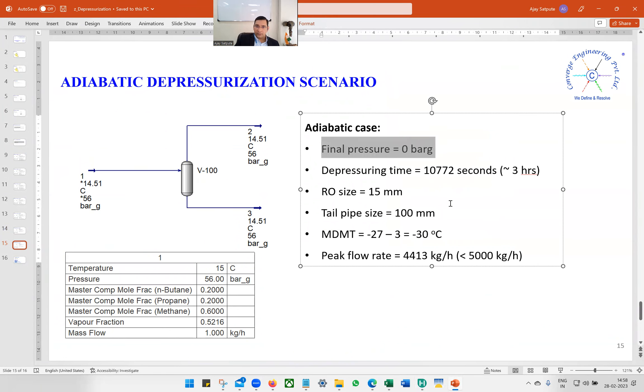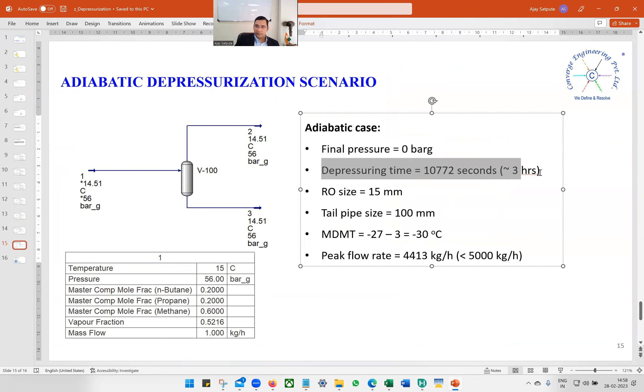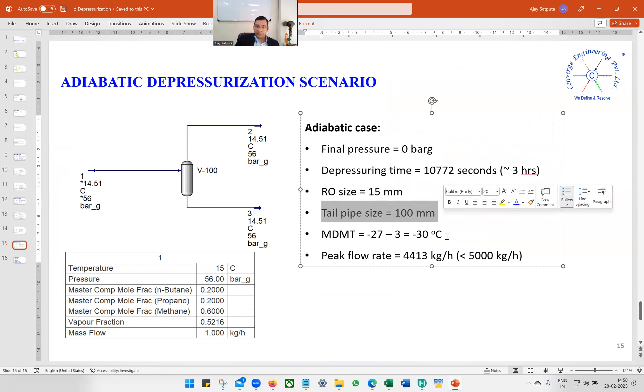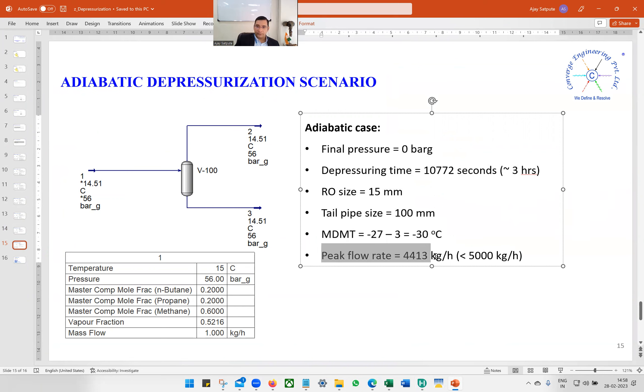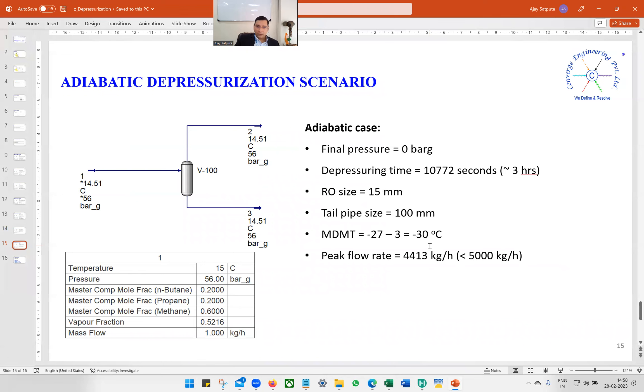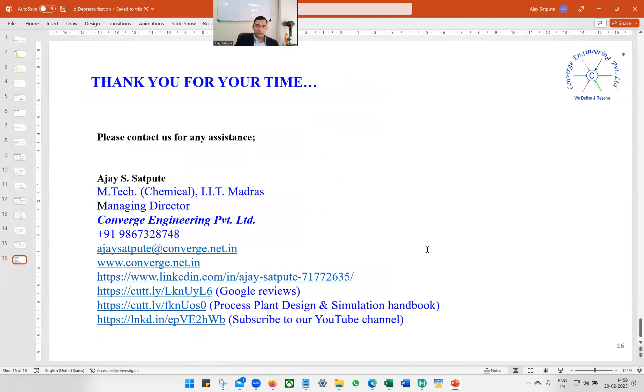In summary for the adiabatic case: final pressure is zero bar gauge, depressuring time is approximately three hours, RO size is 15 mm, tailpipe size is 100 mm, MDMT is minus 30°C, and peak flow is 4413 kg/hr. This is how we do depressurization using the blowdown utility in Aspen HYSYS. Thank you for your time — if you have any questions or queries, please write your comments.